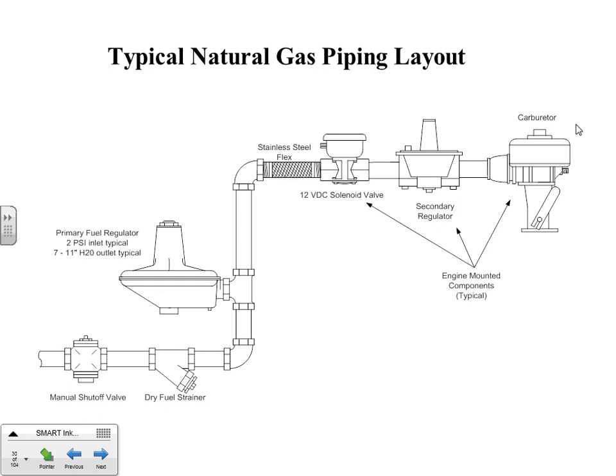This is what a typical natural gas piping system looks like. First of all, in the pipe, and this might be 2 psi out here. You know, that's a very common supply line like you might have in your house for natural gas. Got a manual shutoff valve here, a strainer, which heavier particles in the fuel will drop down here, and you clean them out every now and then. Comes on up again 2 psi into a primary regulator, and that regulator on the inlet here is 2 psi, and the outlet is 7 to 11 inches of water. That's the size we like to see.